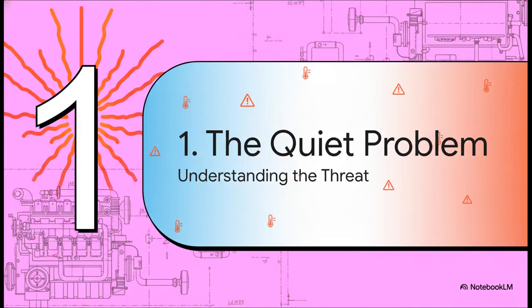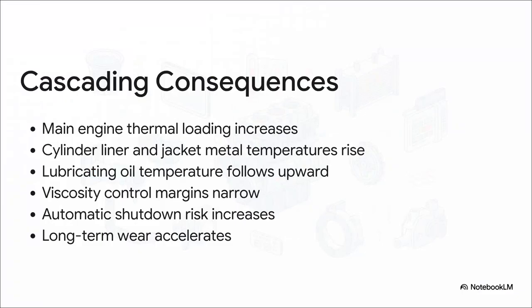Let's be perfectly clear. A rising temperature is never just a number you log. It's a direct warning. It means the thermal balance of your engine room is moving away from its design conditions. The system is telling you, very clearly, that it can no longer get rid of heat as fast as the machinery is making it. And when that balance is lost, the consequences cascade to the entire plant.